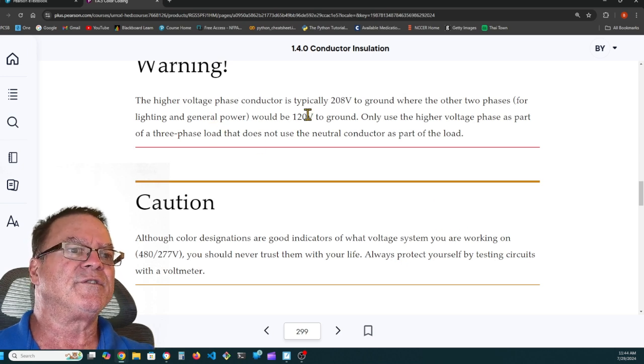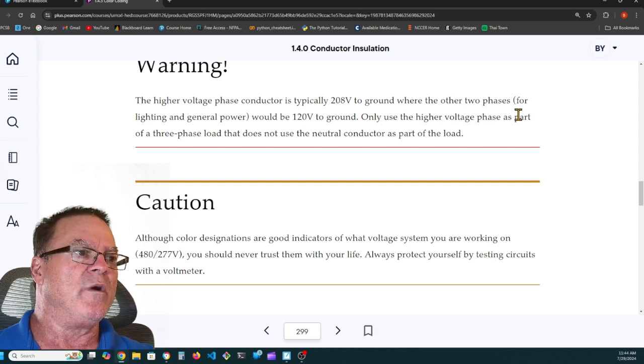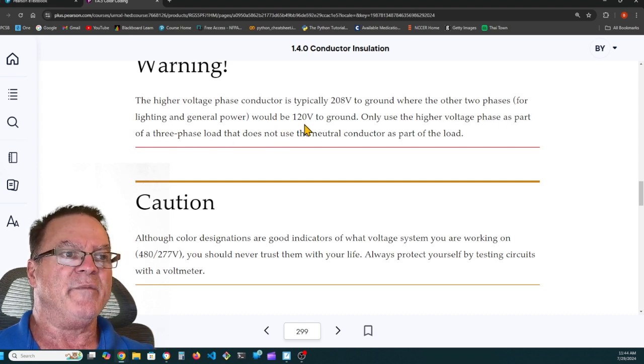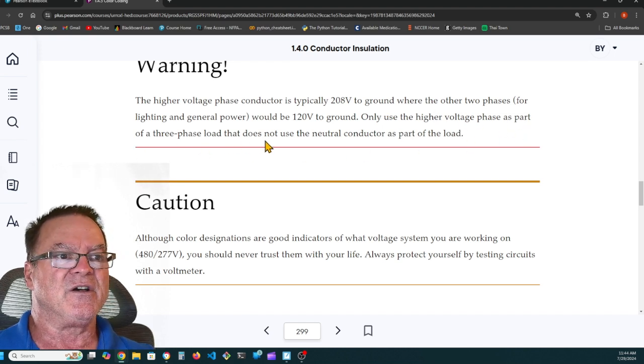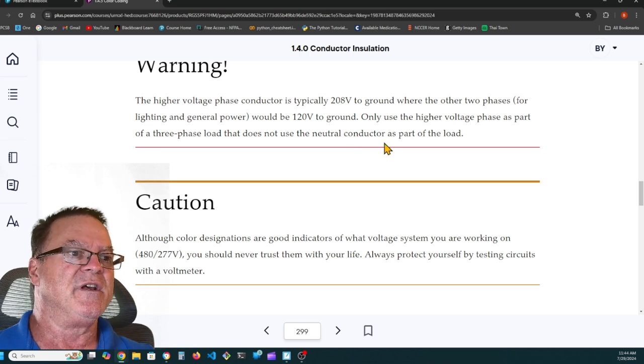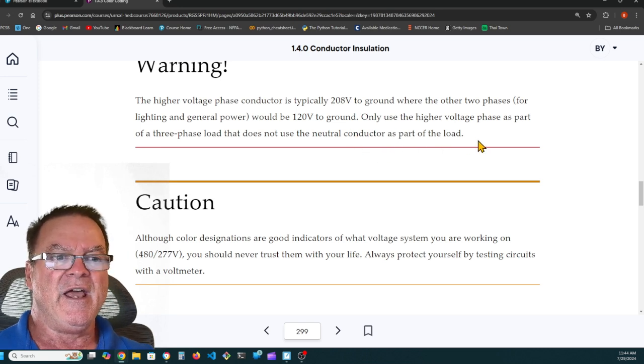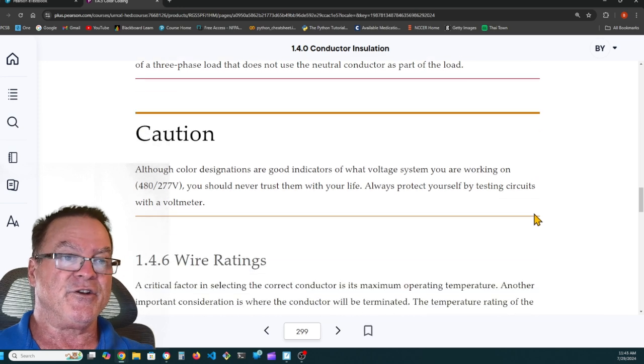Warning, the higher voltage phase conductor is typically 208 volts to ground, where the other 2 phases would be 120 volts to ground. Only use the higher voltage phase as part of a 3-phase load that does not use the neutral conductor as part of the load. If you accidentally put a circuit breaker on the B phase of a 3-phase panel, if it's delta, you're going to have a receptacle that has 208 volts instead of 120 volts, and you could burn stuff up.